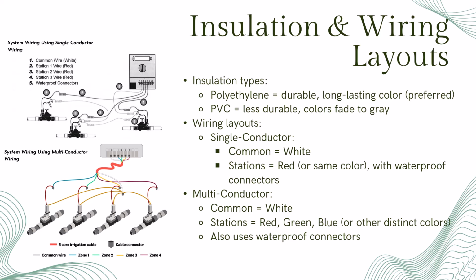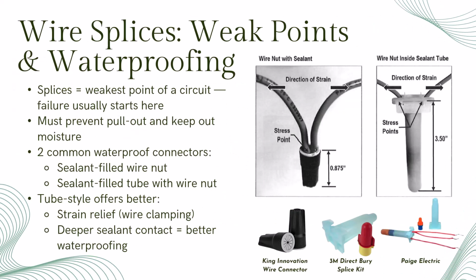For system layouts, most setups are either single conductor or multi-conductor. With single conductor, you'll often have all red valve wires and a white common. It works great, just make sure you're using waterproof connectors at every splice. With multi-conductor wire, you'll get a bundle of different colored wires. Makes it easier to keep things organized, especially on bigger systems. Just like with single conductor, waterproofing those connections is key.